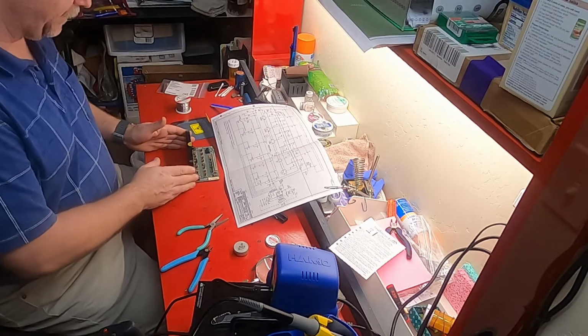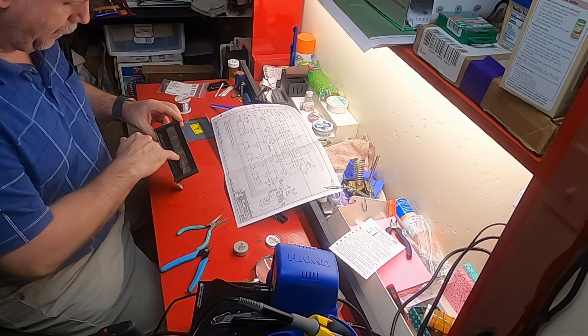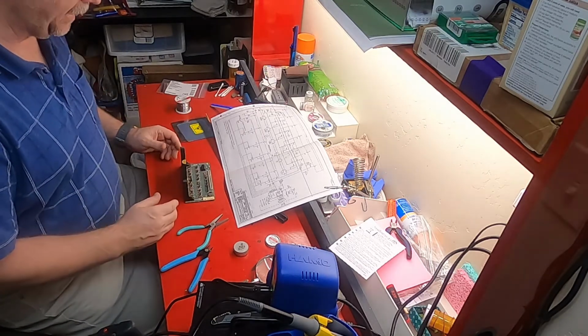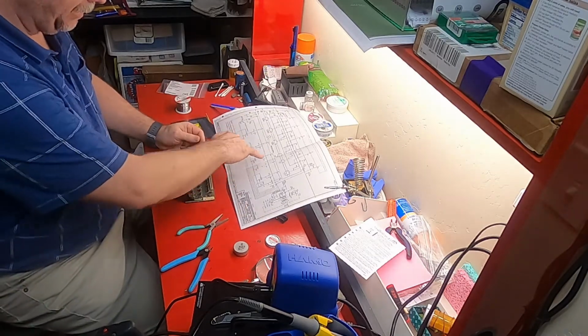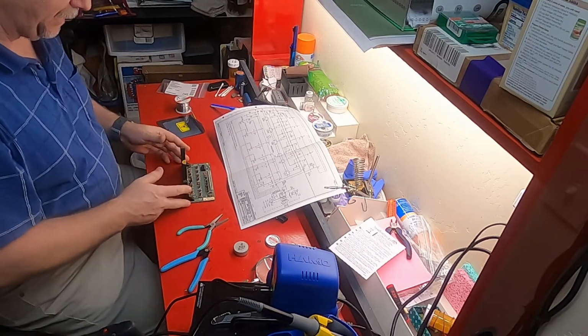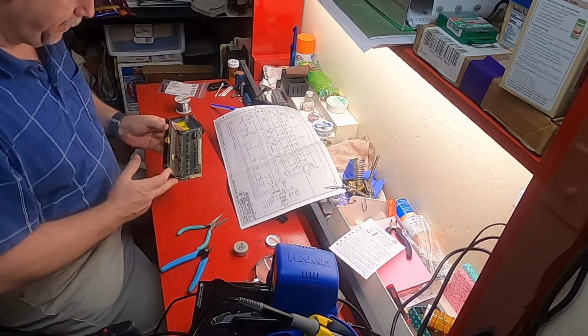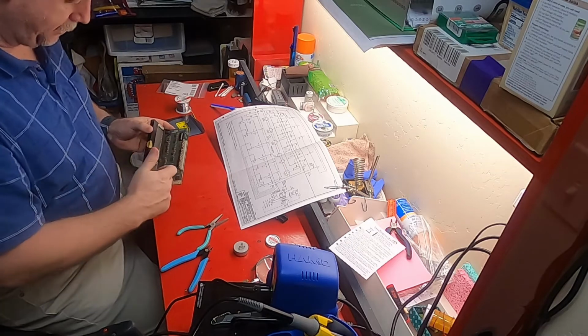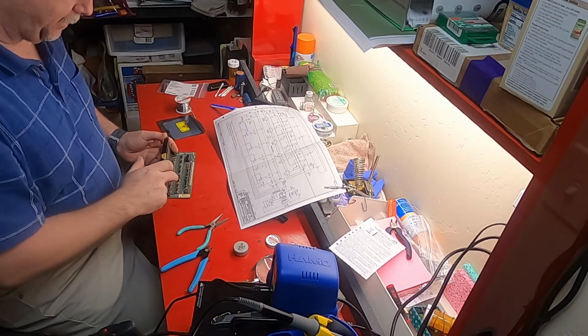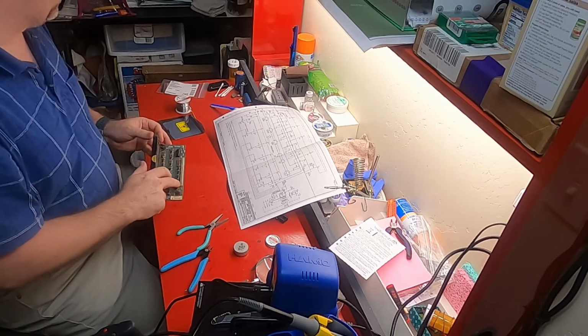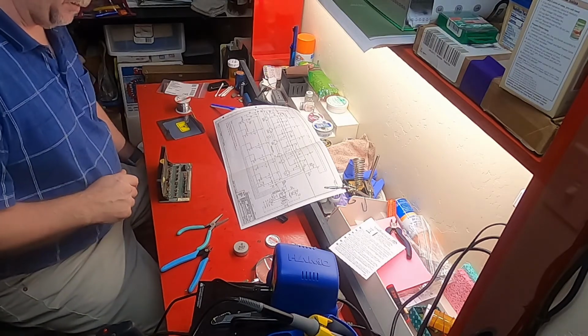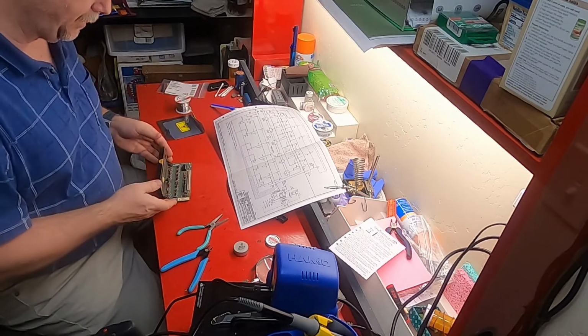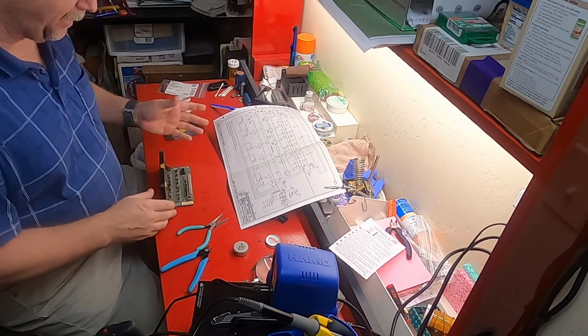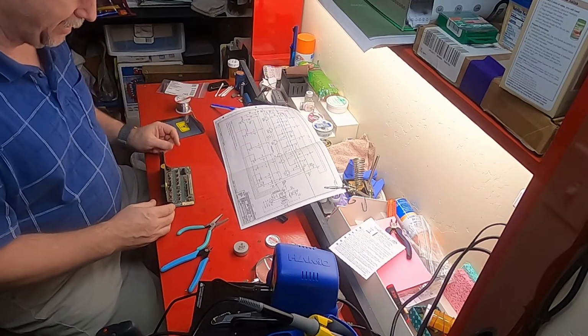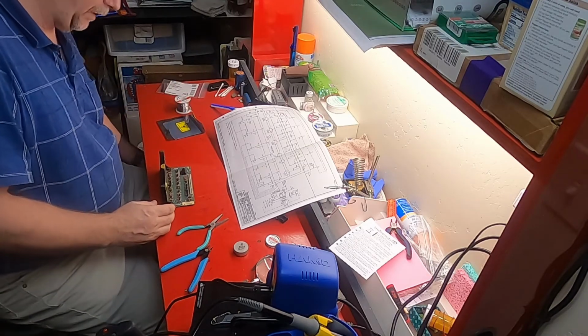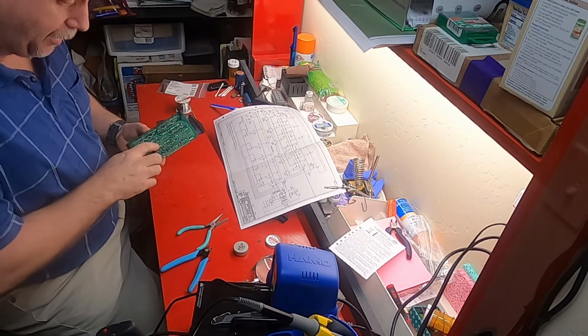So where we left off was display 4 had the lower left segment on all of the digits out. That indicates the segment driver, in this case segment E, is not working. Most likely cause is Q17. Be careful, because there are two different types of transistors on this board: the MPS A42s, and the 2N5401s. They are not compatible, so don't mix them up. Make sure that when replacing Q17 you put in the right type of transistor. That's the most likely cause of a segment failure. It could be some resistors causing the problem too, but Q17 is most likely. So far my luck with most likely causes has been pretty nil, so we'll see how this works out.